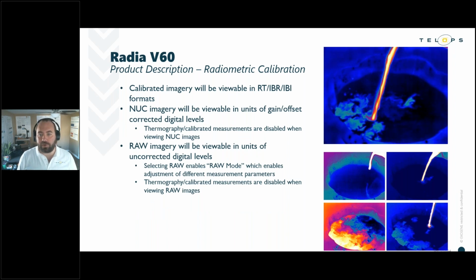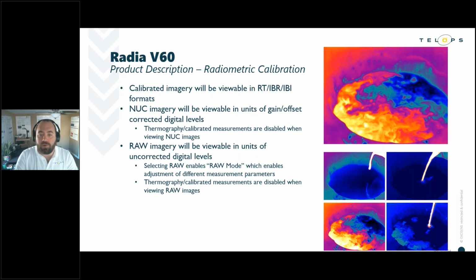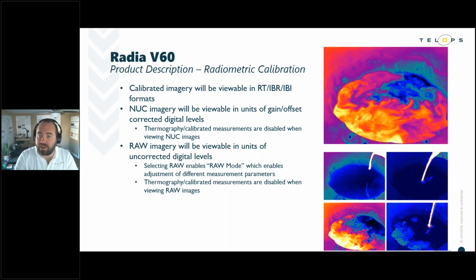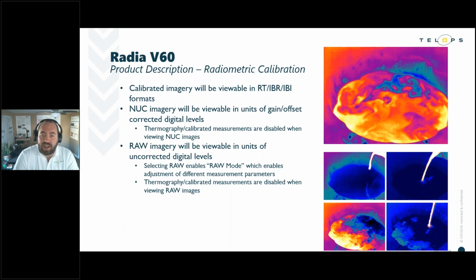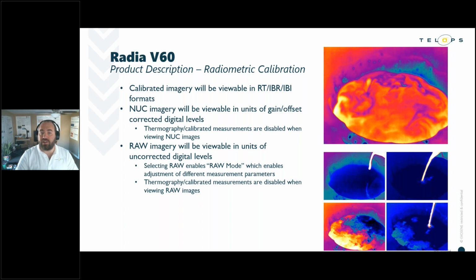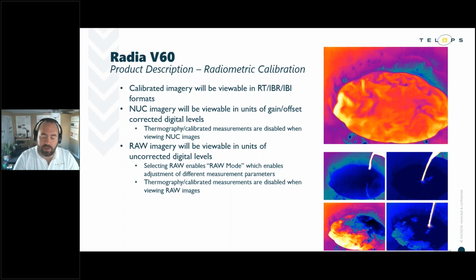Our calibration is really designed to give maximum flexibility to the user. As a result, we've enabled the ability to switch between these different calibration modes at will. We first have the calibrated mode, which allows us to assign a physical unit to the detector signal and view the collected image in units of temperature, radiance, or irradiance. The user also has access to the NUC imagery, the non-uniformity correction imagery, which allows the data to be viewed in units of digital levels with a gain and an offset correction applied. And then finally, we have the raw data always available: uncorrected raw data, viewable in units of digital levels, just like the NUC mode. So remember that when you select the raw mode in RevealIR software, this enables our advanced user mode, where the user has additional flexibility with the measurement parameters that is prevented when we are using these calibrated data outputs.